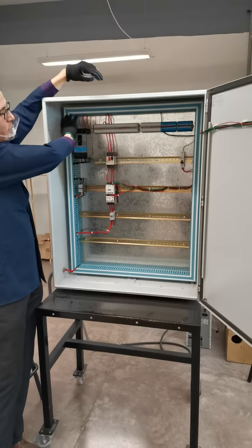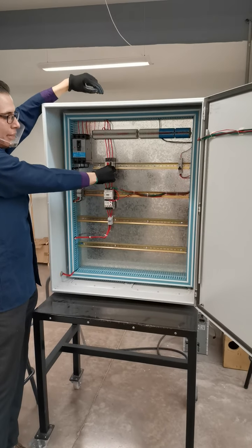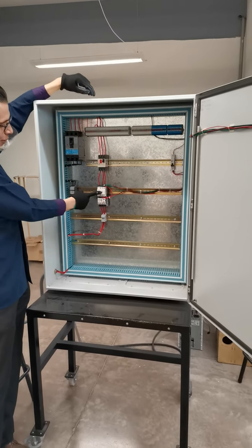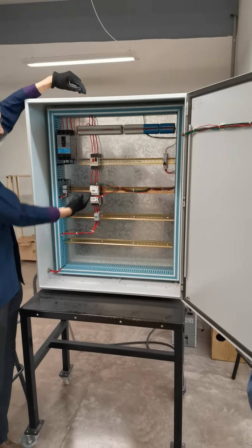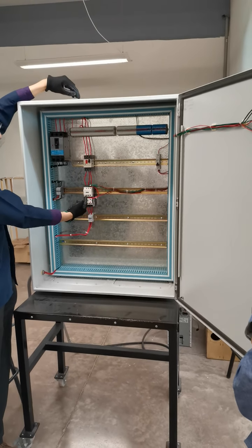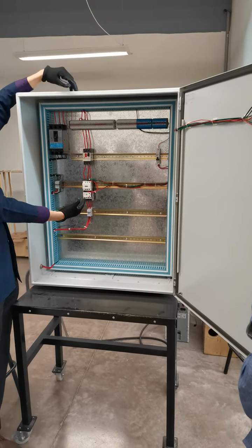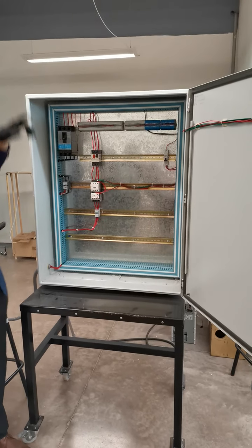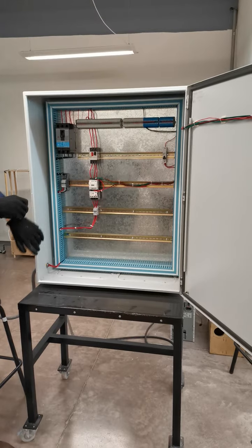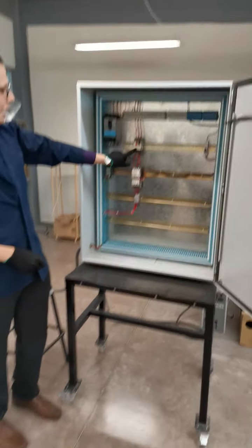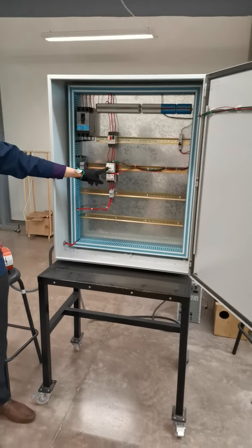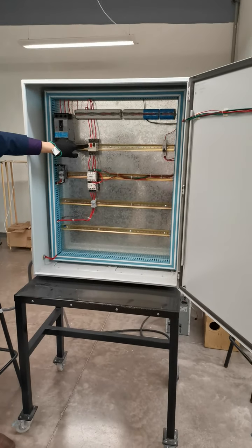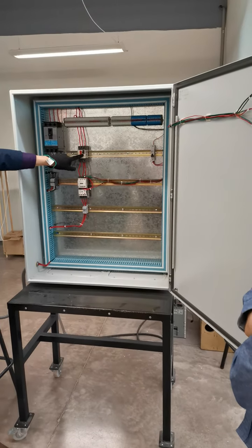So from the main power line, we have this derivation for this disconnector that is connected to the motor starter. The motor starter is a combination, if you remember, of a contactor and an overload relay. The overload relay is for current protection and the contactor is for electrical activation. Because if you remember, we already said that this one over here and this one over here are basically the same. The only difference is that this one over here has an overcurrent internal protection, but it's a mechanical activation.